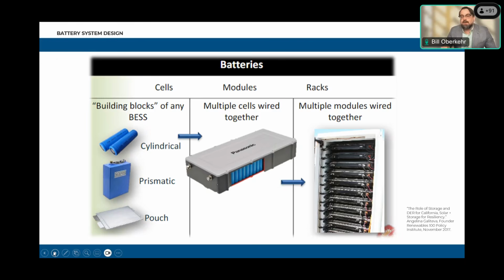Cells wired together create a module, and modules wired together create a rack. Racks wired together create an installation. This will be relevant when we talk about large-scale fire testing, the UL 9540A testing, because that test can be done, and often is done, at each of these levels. So commit this to your short-term memory: cells are the smallest, modules are cells wired together, and racks are modules wired together. Next slide, please.